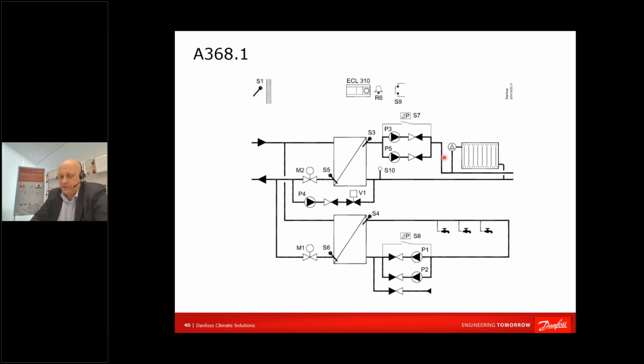Yep. And as you said, you can use everything from your pump, only then it might be a little bit tricky how to tell someone somewhere that your pump is struggling. In this scenario, it's quite simple. If you had a Delta P alarm, then you are sure that something has happened. If you would use a smart pump with some communication language, instead of an ECL you would probably want to see some PLC, and then again you will spend the price of 4 ECLs to write an algorithm to discover it. So both things can live separately. Yep. So yeah, okay. You can do both. I would personally recommend Delta P, because it's bulletproof. It's simple.